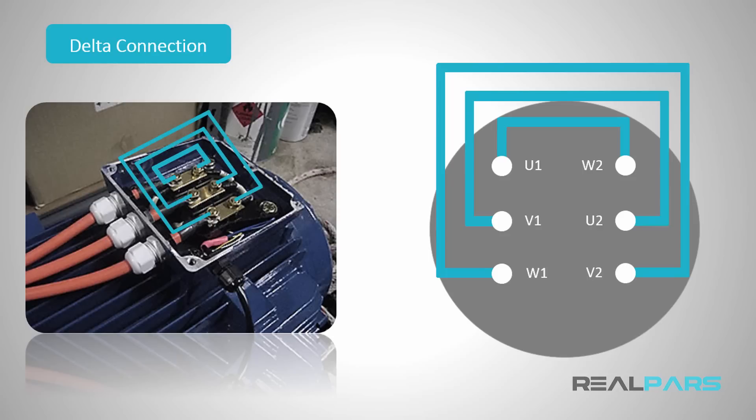To limit the current that the motor draws in the startup phase, you need to start the motor in star connection first. When the motor gains sufficient speed, the connection should change to delta.